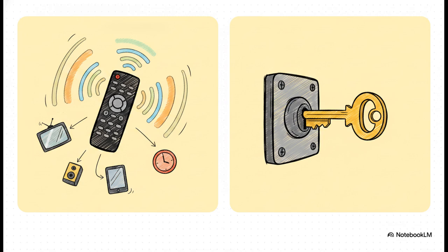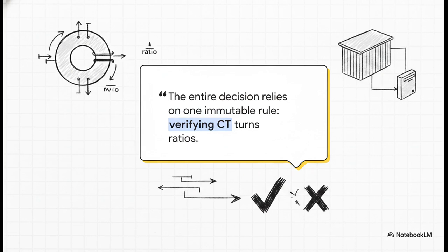Choosing between low and high impedance REF is a lot like choosing between a universal remote and a manufacturer-specific deadbolt. Low impedance REF is that universal remote, right? You can reprogram it through software to adapt to mismatched equipment and completely different systems. High impedance REF is the deadbolt keyed to one exact lock. It demands that every single piece of hardware matches perfectly, but once it does, nothing beats it for keeping that one specific door secure. So how do you actually choose?